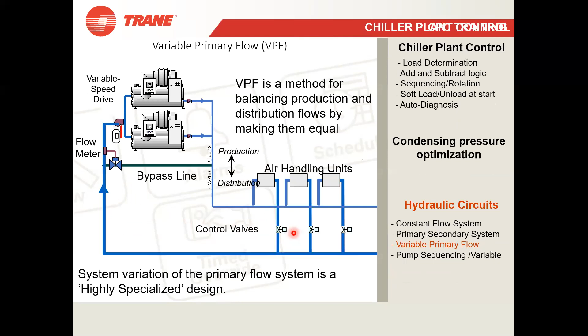Now this slide tells what I told you on the previous slide. What are the variable primary flow principles? Just as in the primary-secondary system, you can read this. VPF responds to load changes by modulating flow, but the only difference is there is no secondary, only primary. In a VPF system, water flow varies throughout the entire system, that is through the evaporator of each operating chiller as well as through the cooling coils. And the system elements, I have shown you all of them, right? Two-way control valves on the coil side are everywhere. You can see on my previous slide, these are the two-way control valves. All the AHUs have these.